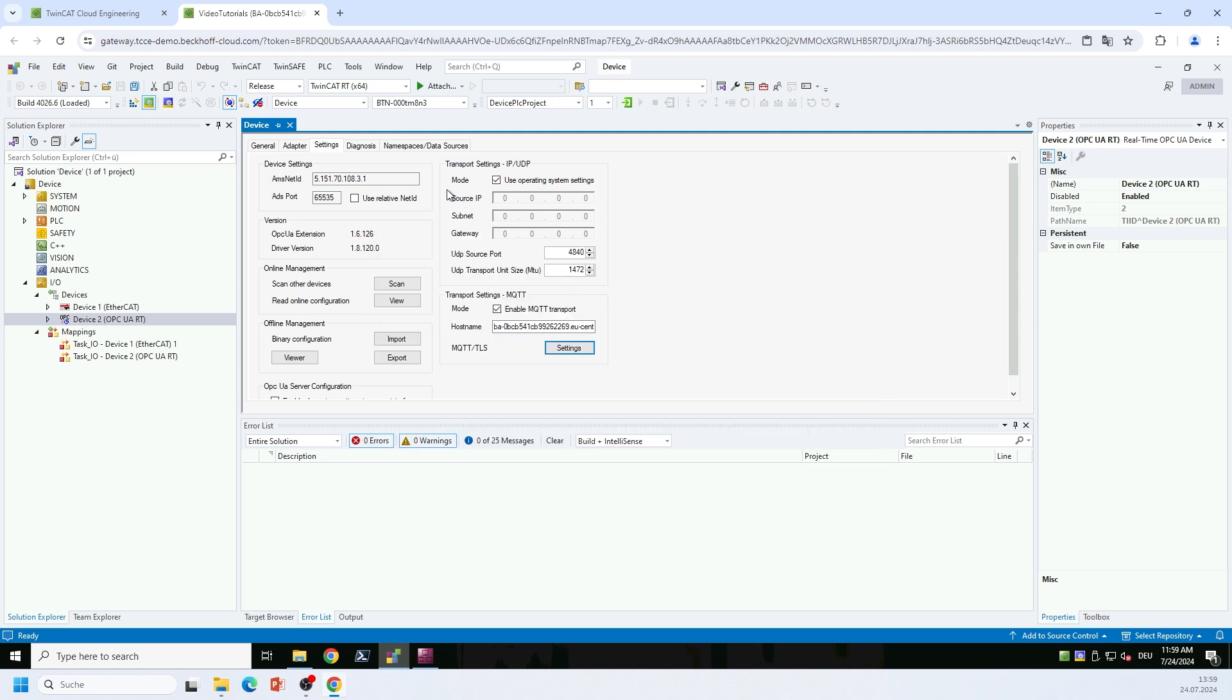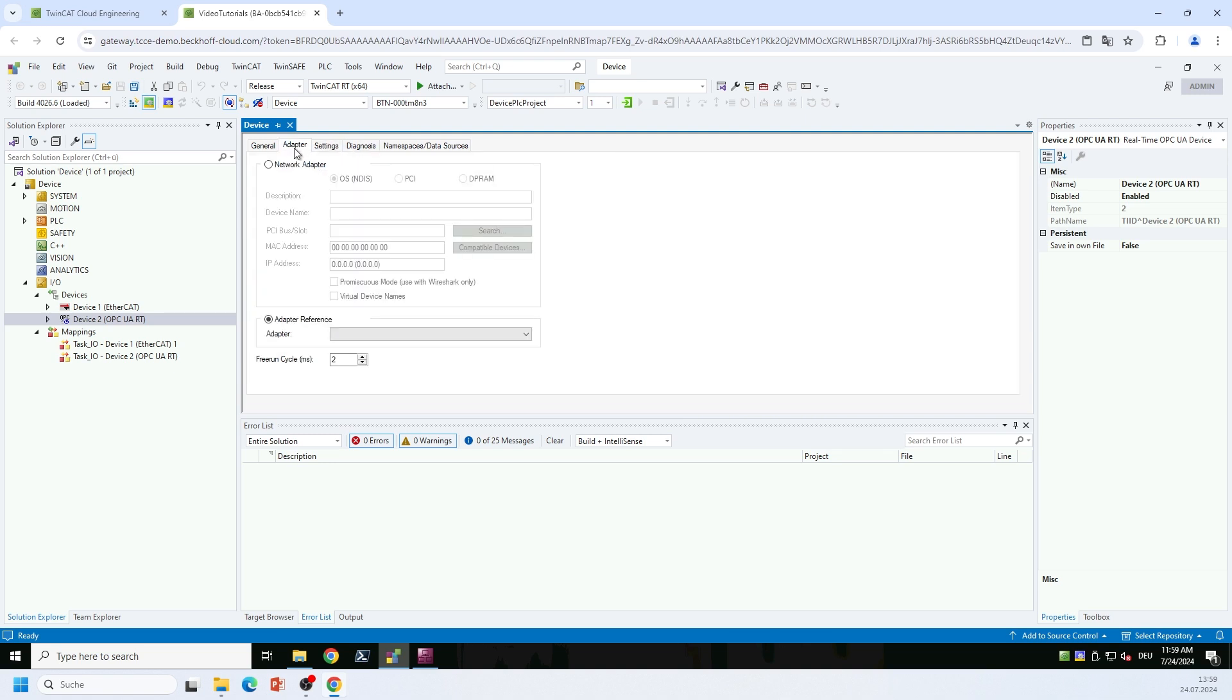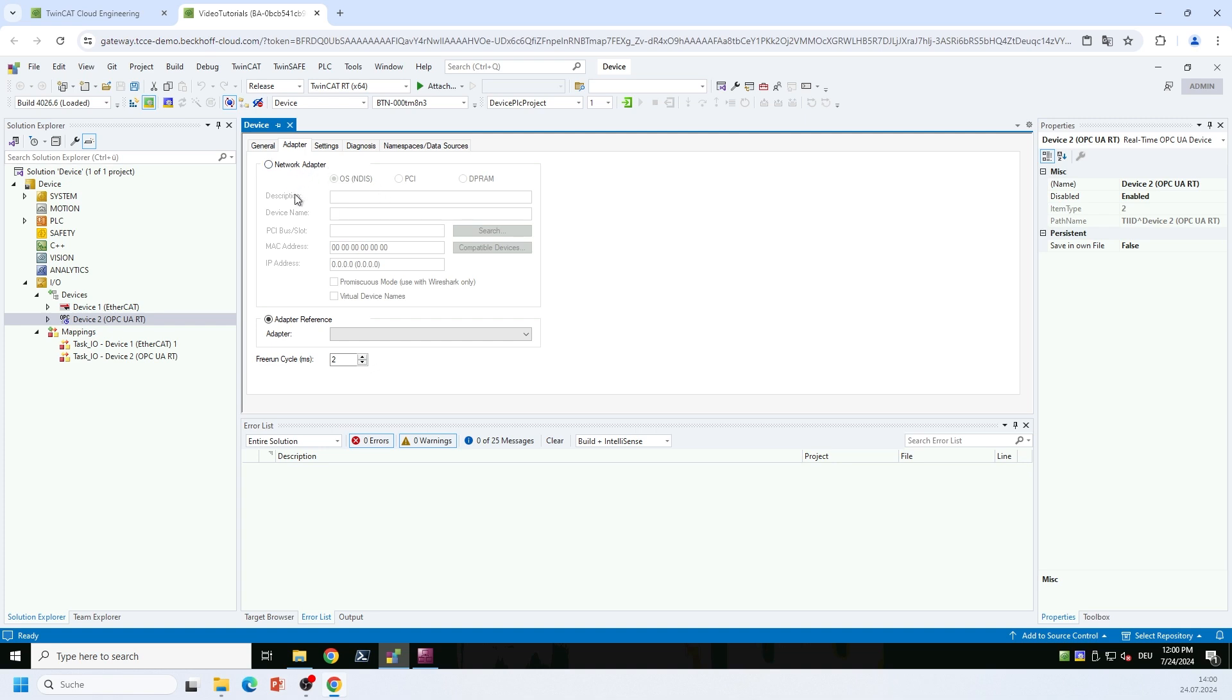So the next thing that I need to do is I need to set up my adapter settings here on the adapter tab. With TF6105, with our OPC UA PubSub implementation, if you only want to use MQTT, you don't need to select an adapter reference here because the MQTT implementation is using kernel sockets and it doesn't require our TwinCAT real-time ethernet adapter. Only if you want to use the UDP transport, you need to specify a TwinCAT real-time ethernet adapter here on top of this dialog.